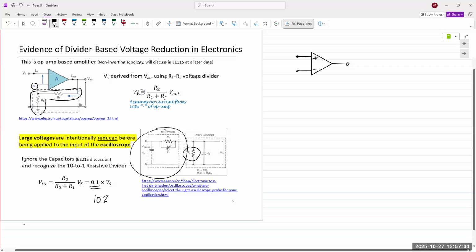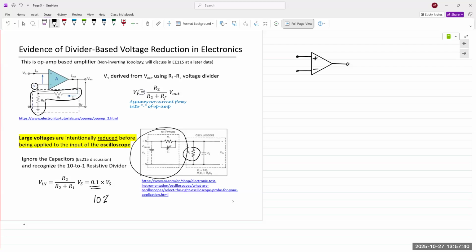Technically, all these oscilloscopes that we use in the lab benches, they can measure up to 300 or 400 volts. It'll be listed in their specifications as well as on the front panel. So don't do this, but technically you could take a probe, put it on 10x mode, and you could possibly stick it into the power outlet.